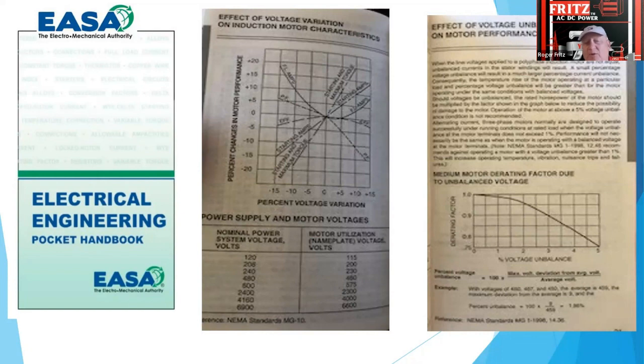This is part of the reason why, when you put a VFD on, because we're isolating the input from the output, we're able to still control that voltage balance. So we've literally seen where you can run really imbalanced voltages out on the primary, but with a good VFD, you can actually regulate each of those phases into balance, so you don't have to upsize, and the motor will run a lot cooler.